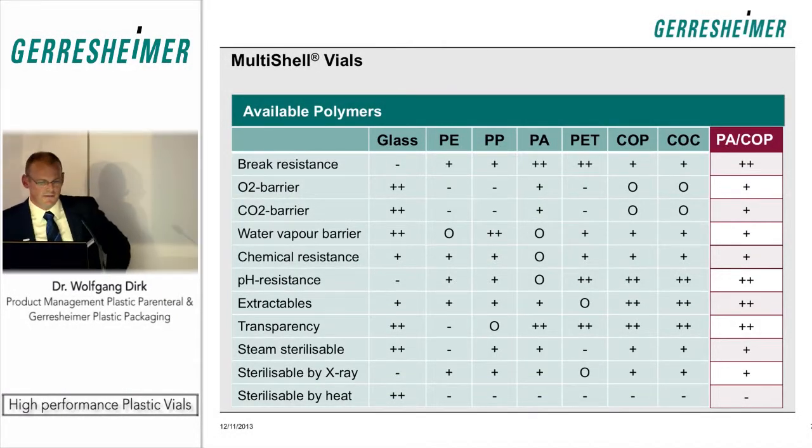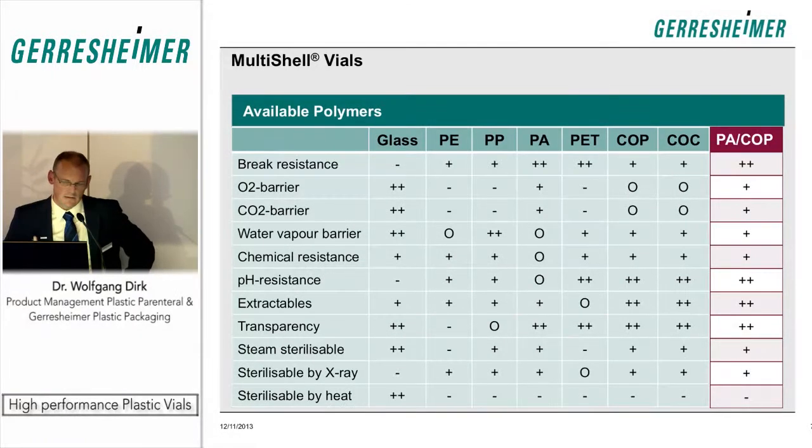When we developed the vials, we screened the specifications that plastic vials need to meet as a replacement for glass vials. You can see the most important requirements in the table: break resistance, gas barrier, chemical resistance, pH resistance, and so on. We compared these against the major materials available for plastic vials. Glass, as the reference, performs very well — marked with a double plus on several requirements — which is why it has been the dominant material for these containers.